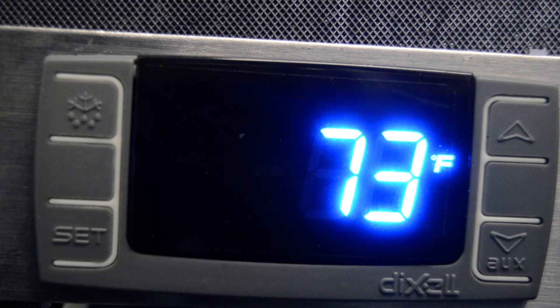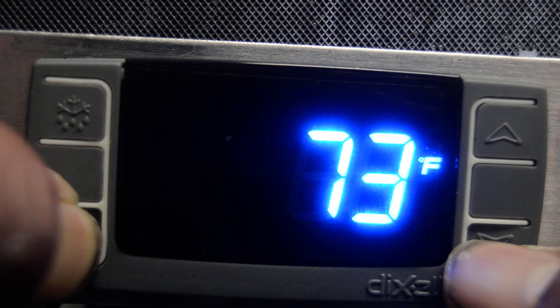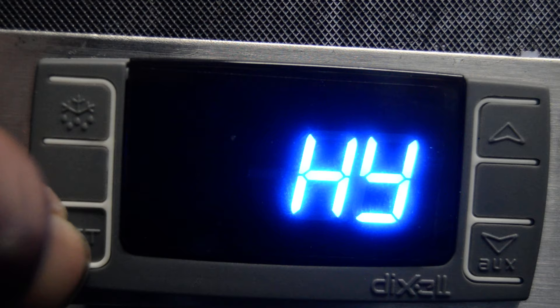Whenever we have a Dixell controller, like the one here, and we're trying to set the defrost timing to be a little bit different, you're going to start just getting into the settings by holding down the SET button and the down arrow together until it reads HY. At that point, we'll let go.